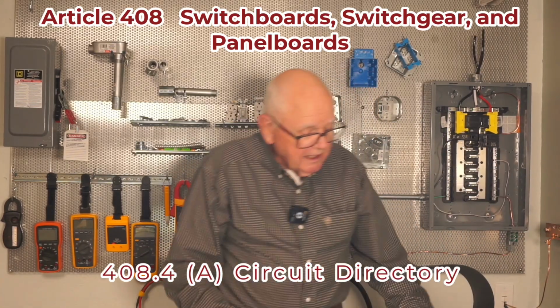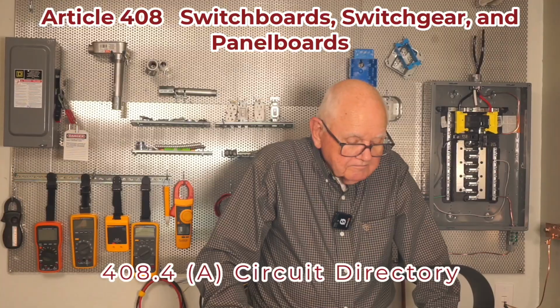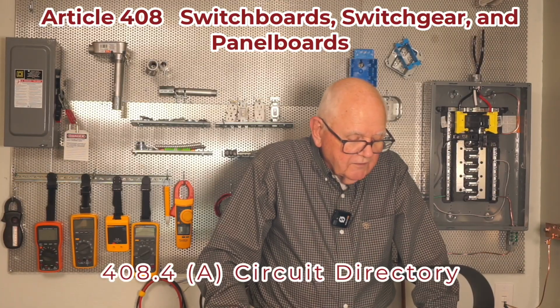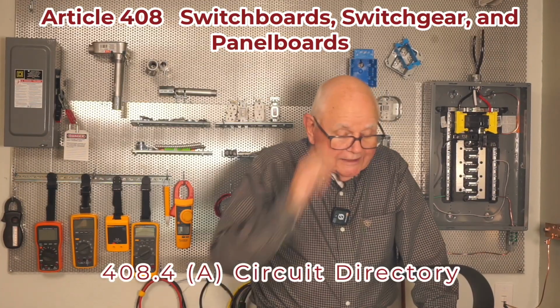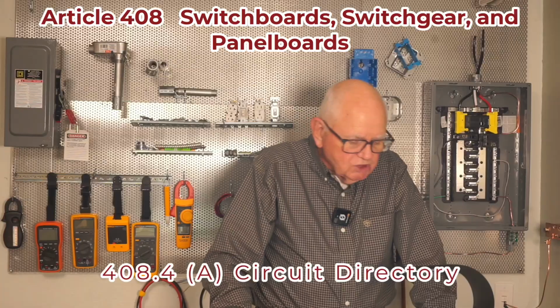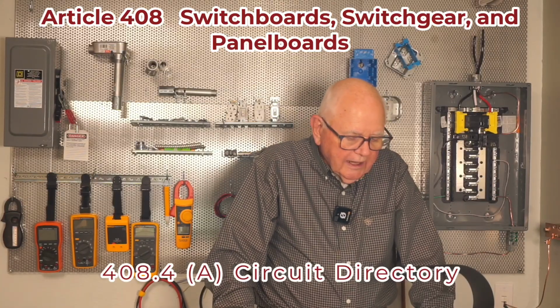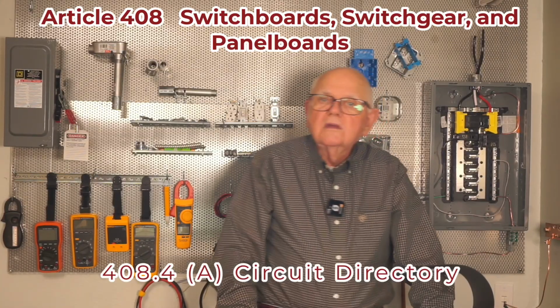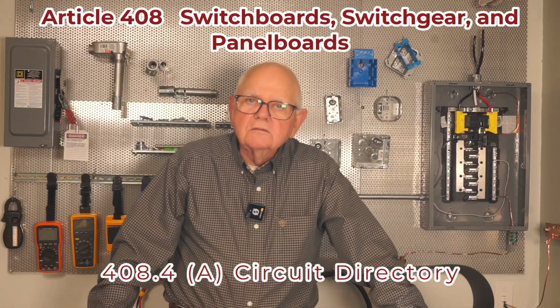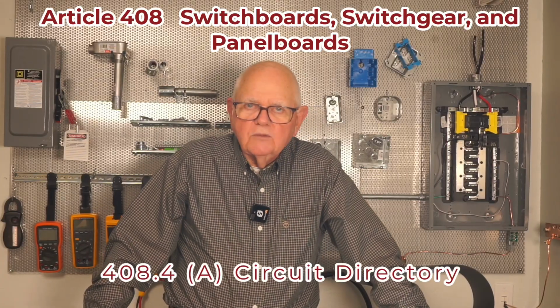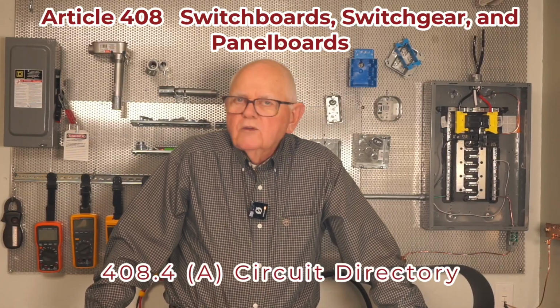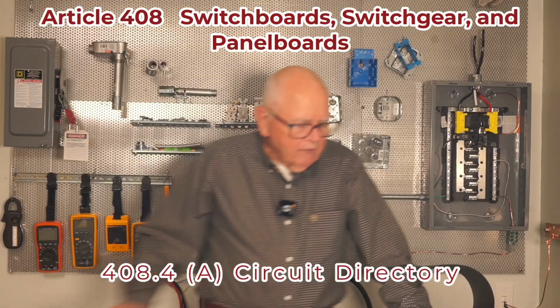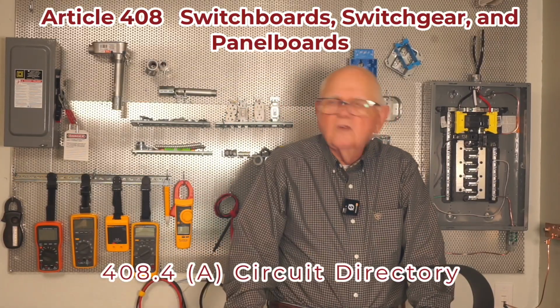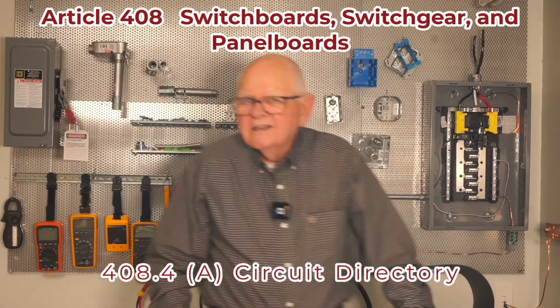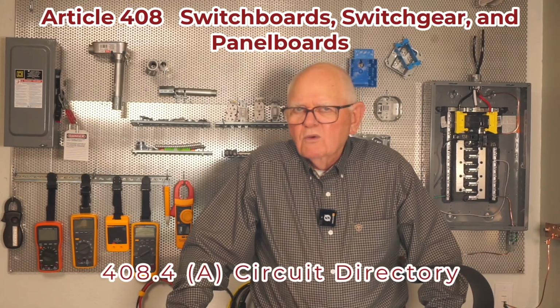It tells us. It says it is located on the face of or inside of the door, or in an approved location adjacent to the panel, in the case of a panel board. So I don't have to have it inside the door. It could be adjacent to the panel board somewhere, an approved location. Where do we always find it? Inside the panel board. Now, if we look at the rest of those requirements in 408.4(A), here's what it's telling us on the directory requirements then.